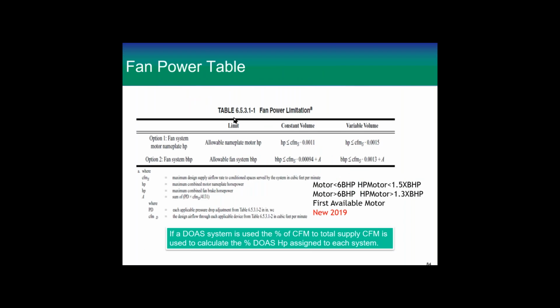Now, you take that horsepower. This is a constant volume. This is a variable volume system. This is option 1, where we're going to use the nameplate horsepower. You take that horsepower, you add it all up, and for a variable system, let's say, your horsepower has to be less than the CFM through that main supply coil and fan times 0.0015. Constant volume is a little lower, 0.0011. All right, so that's the allowable nameplate horsepower.